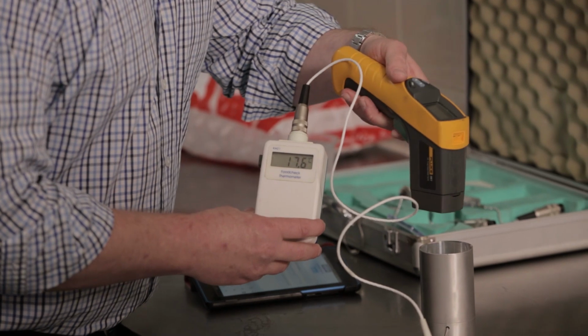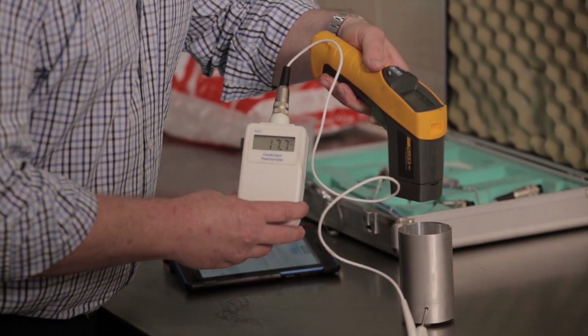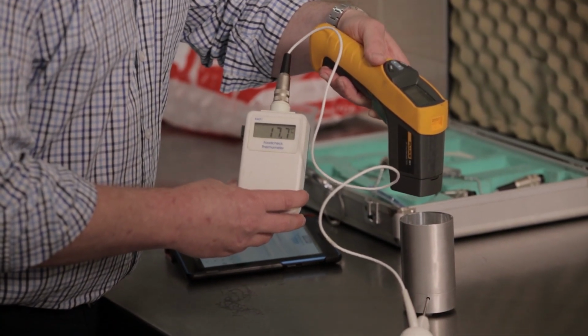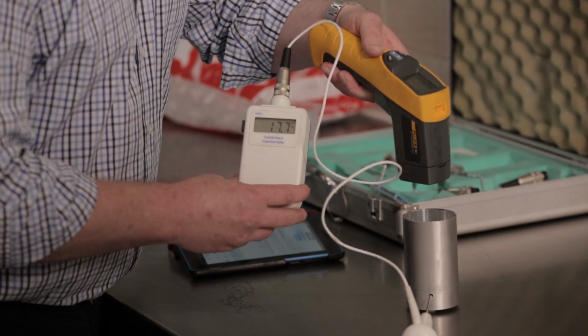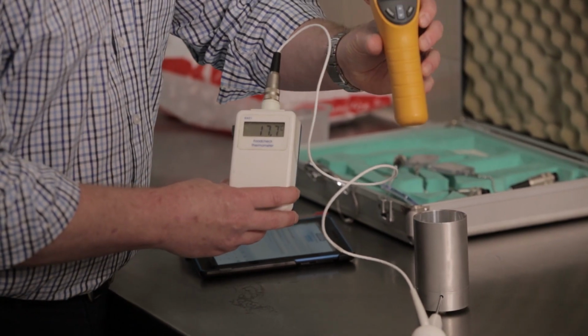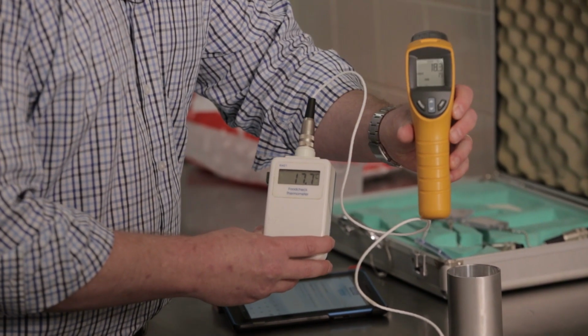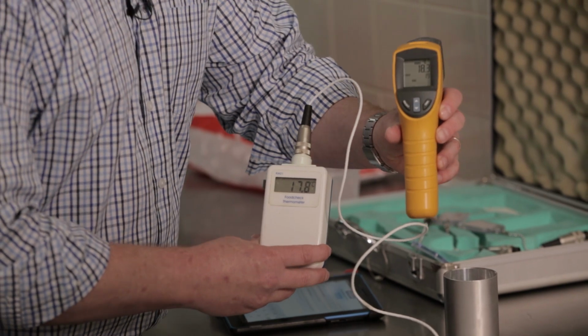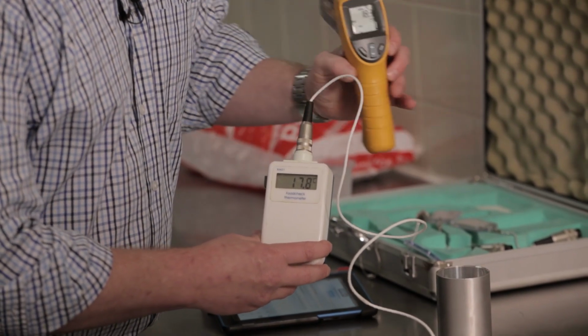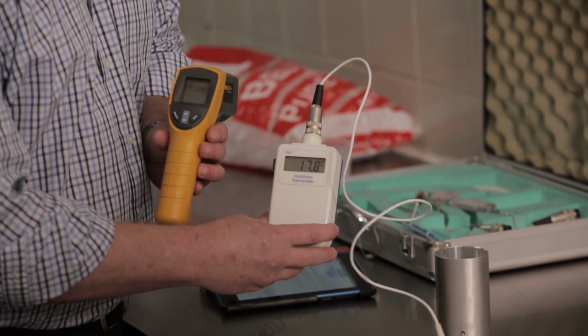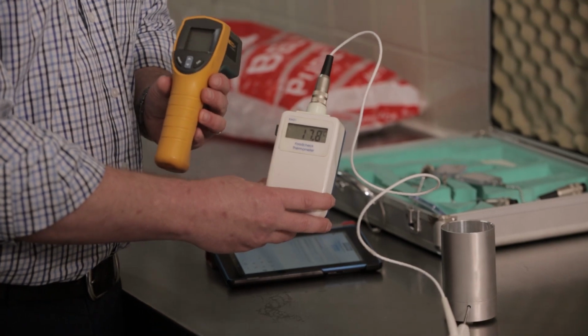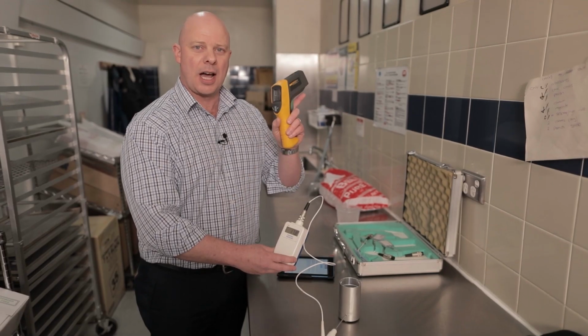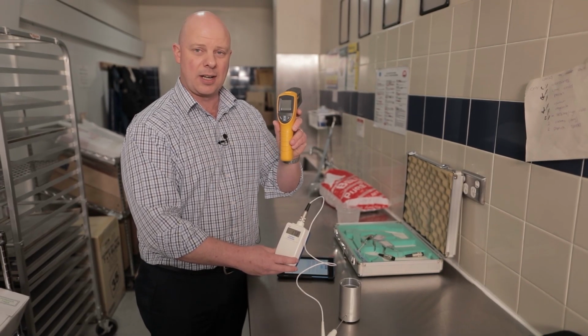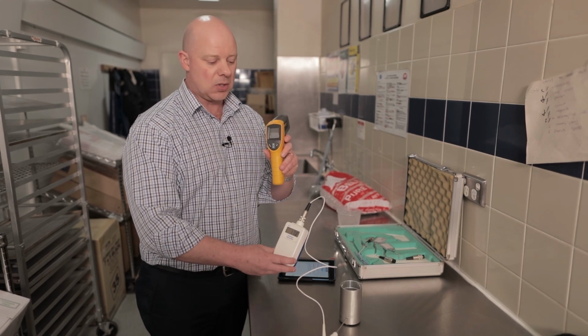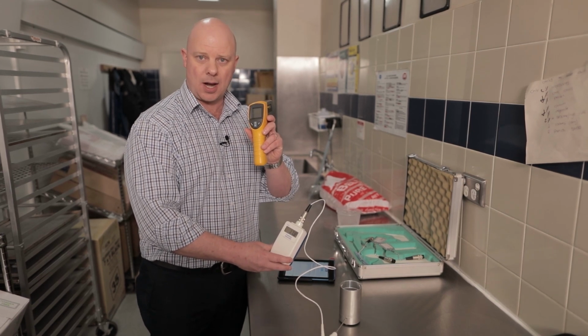And I want to point this infrared gun into the center of this cylinder. And the reading on this gun needs to be within plus or minus 1 degree of the digital thermometer. So we can see it's sitting at 18.3. The digital thermometer is at 17.8. So that's within plus or minus 1 degree. So we're satisfied now that this IR, this infrared gun, is accurate. This is the only way to check the accuracy of this gun.